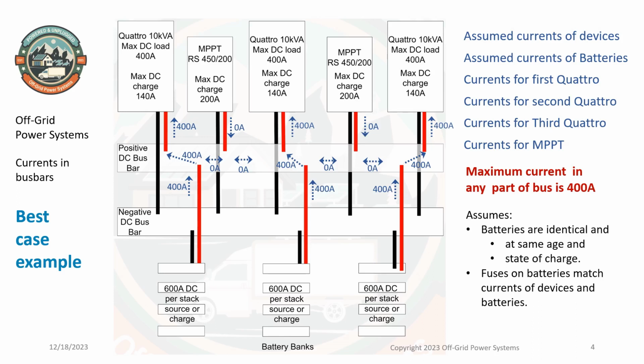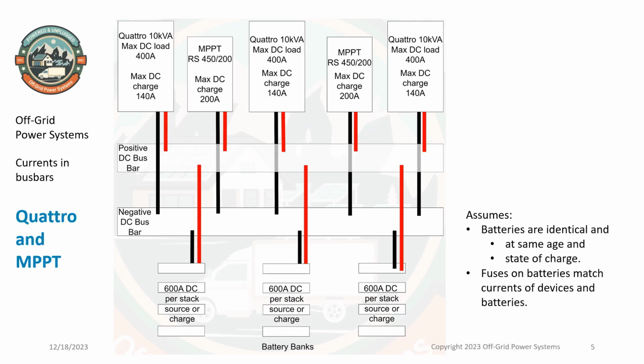Thus, the bus bar can be smaller, saving copper, and since the max current is less, there's less loss of power in the bus bar, and thus more efficient. Note, there is not one place on this bus bar to measure the total battery current. This is not compatible with current Victron BMS systems relying on an external current shunt, but some battery manufacturers can work with Victron BMSs without a current shunt.